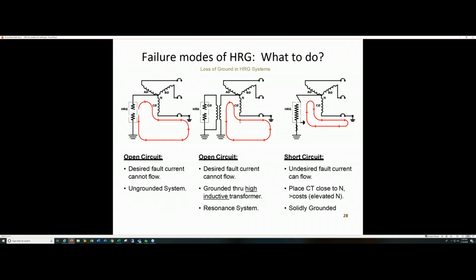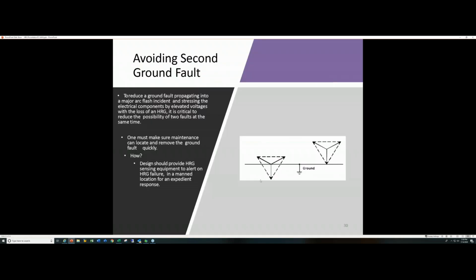Open circuit, when you have this, it's the same thing. This would be a medium voltage system. You would put it through a high inductive transformer, and then you would create resonance. And Serge can talk more about that if that comes up. Short circuit. You could have where the HRG is short circuiting and say it's going around this resistor. That's possible. If you're not maintaining your resistance in your resistor and looking at it and making sure that you're monitoring that resistance is sound, then you could have a short circuit and you're back to a solidly grounded system again. Okay? So the main thing is to avoid the second fault.